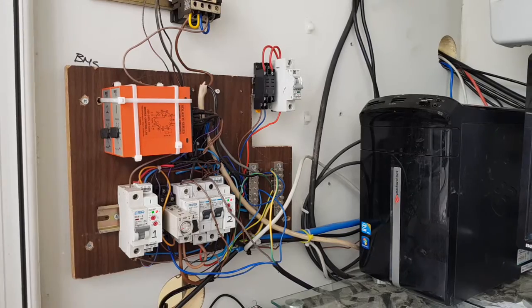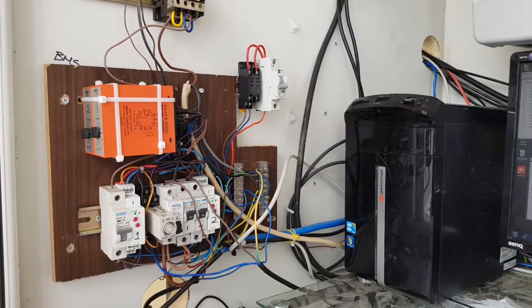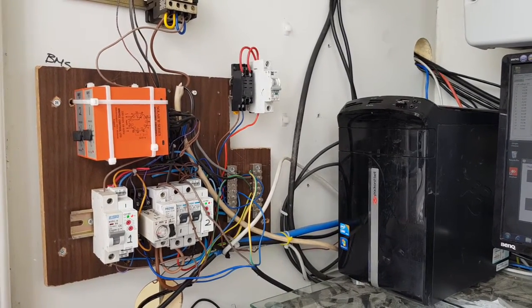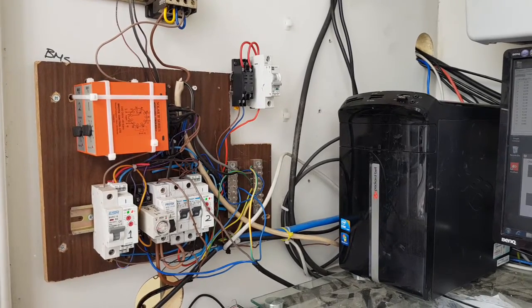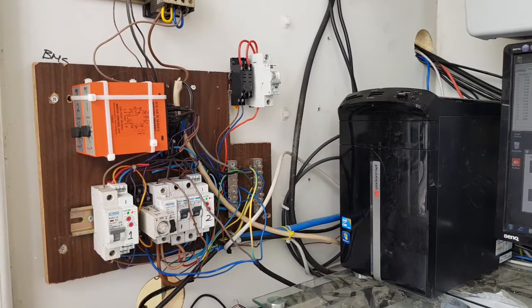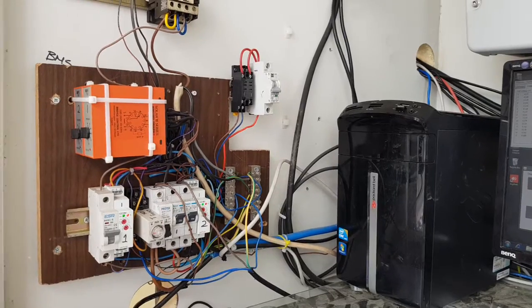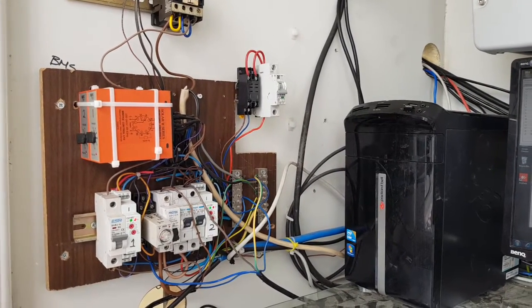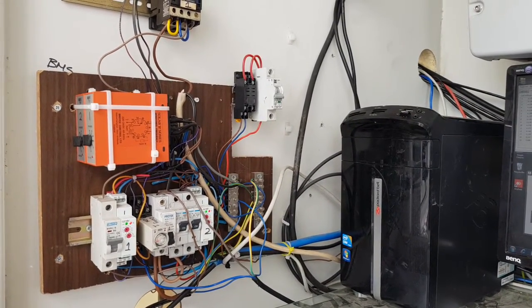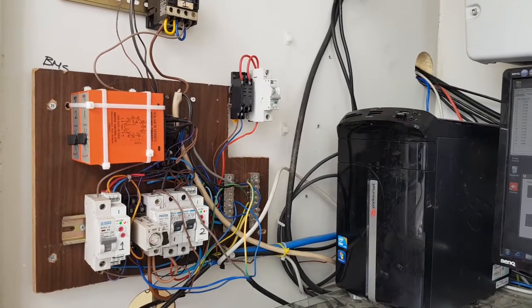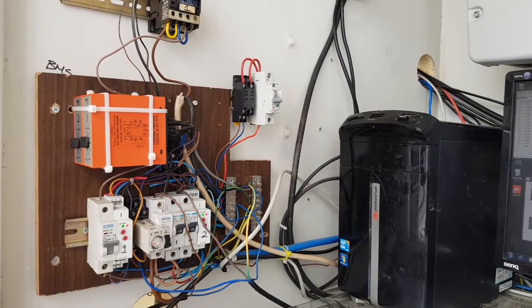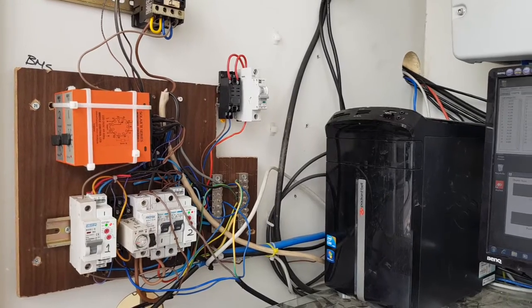When the batteries get too full, it starts to move the frequency up. Here we're running at 50 Hertz on the AC side, so as the batteries get more full, it'll step up to 50.1, then 50.2, until eventually all the other grid-connected inverters understand what's going on with frequency.